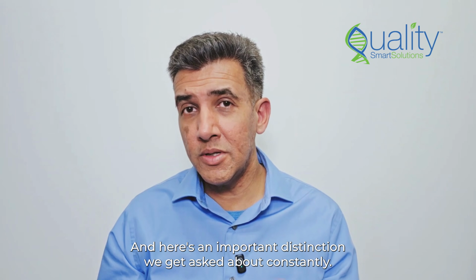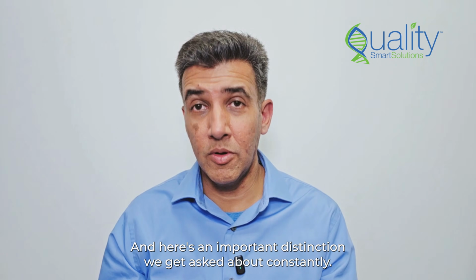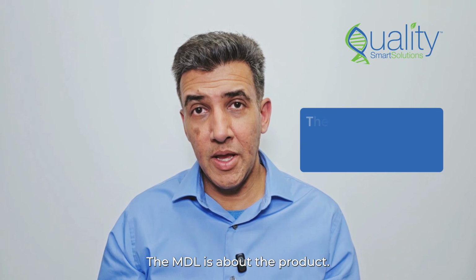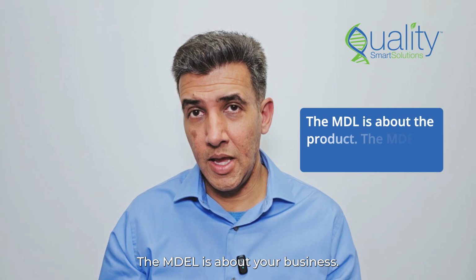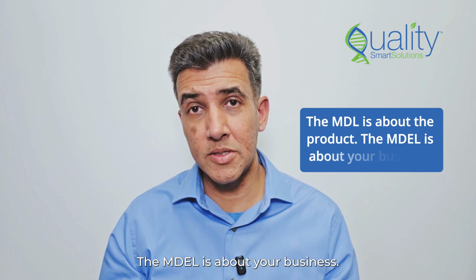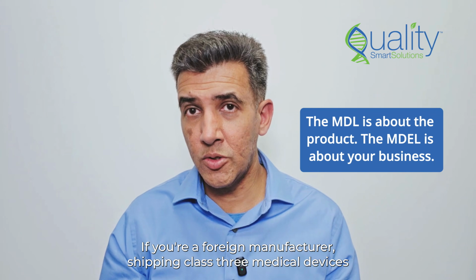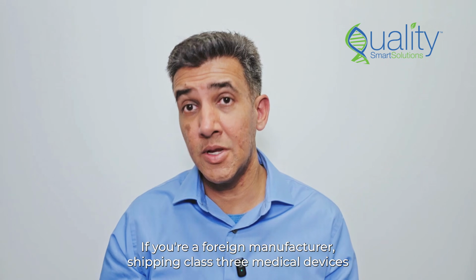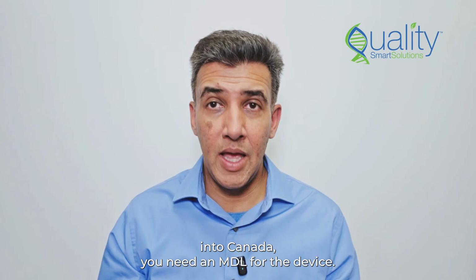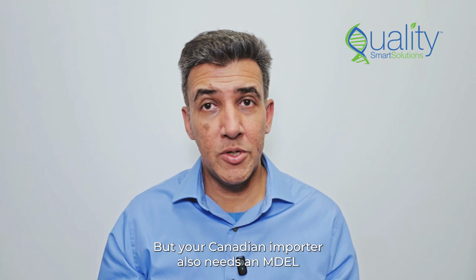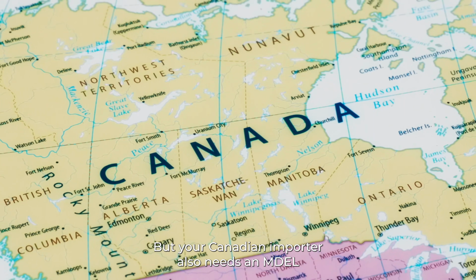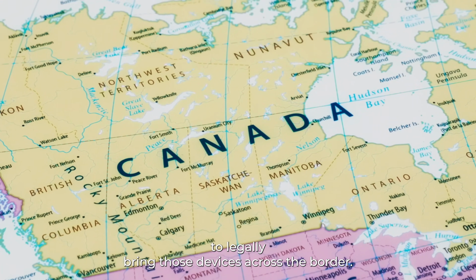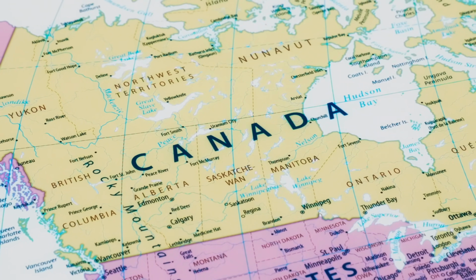And here's an important distinction we get asked about constantly. The MDL is about the product. The MDEL is about your business. If you're a foreign manufacturer shipping Class 3 medical devices into Canada, you need an MDL for the device. But your Canadian importer also needs an MDEL to legally bring those devices across the border.